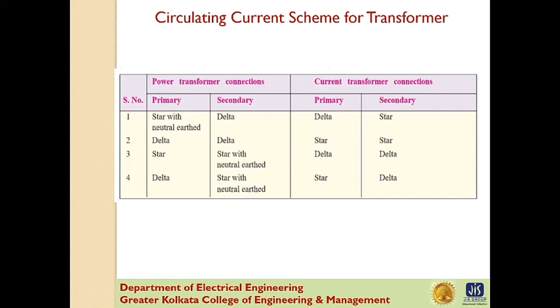In practice, advantage is taken of the fact that initial inrush current contains a prominent second harmonic component. Hence, it is possible to design a scheme employing a second harmonic bias feature, which, being tuned to the second harmonic frequency, only exercises restraint during energizing to prevent maloperation. While applying the circulating current principle for protection of a transformer, these precautions are taken into account to avoid inadvertent relay operation.